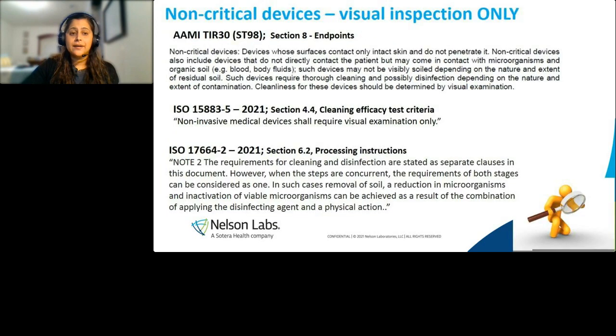One thing that is also coming up is that for non-critical devices, visual inspection is going to be accepted. So we don't have to test for any other analytical markers. Protein, hemoglobin, you just have to wipe and say it was visually clean and we're good to go, which helps manufacturers and also healthcare facilities where we are not adding procedures. When we do non-critical devices, we're adding so much wiping that we destroy the product at the end because we're trying to get to the acceptance criteria.